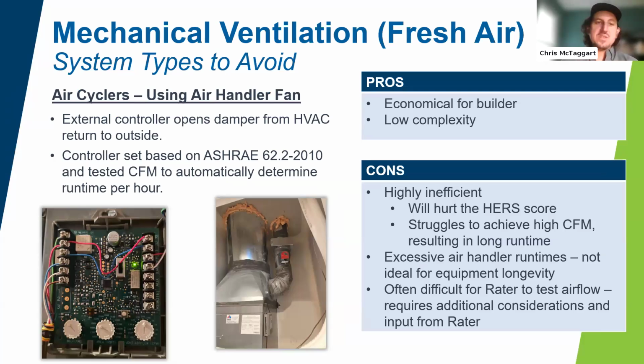You can use a supply-based system, AKA an air cycler. These will take that fresh air duct tied into the return side of the air handler, and then basically set it to a schedule that will ensure that it meets the ventilation needs for the program. The benefit there is that it's relatively economical. It's moderate in terms of complexity. It's not very efficient, though, because we're using our air handler to move around small amounts of air. And so it tends to hurt the HERS score, as well as it means that consumers are paying for their air handler to run. So the consumer actually has to pay for it.